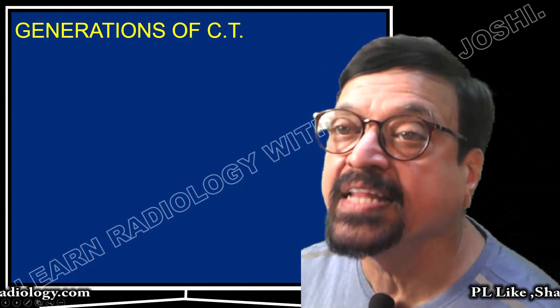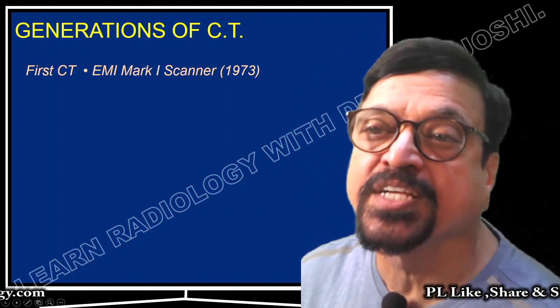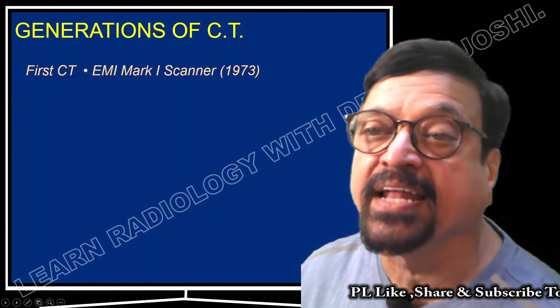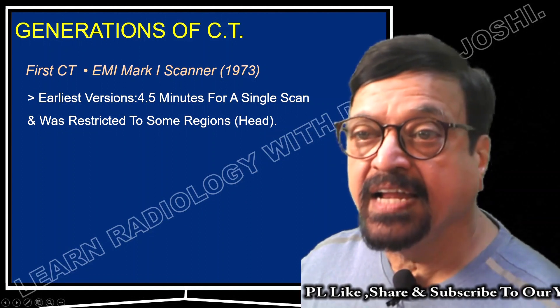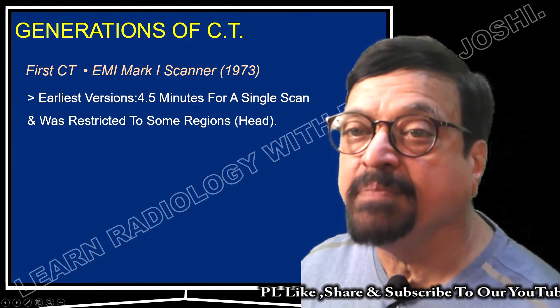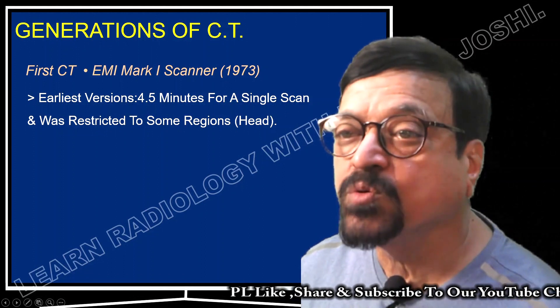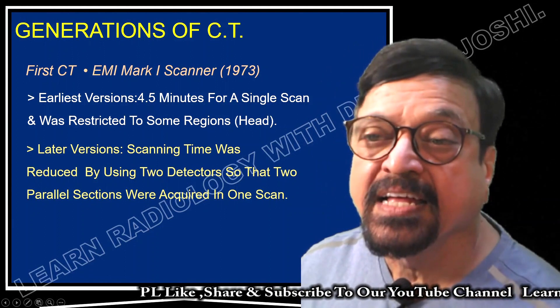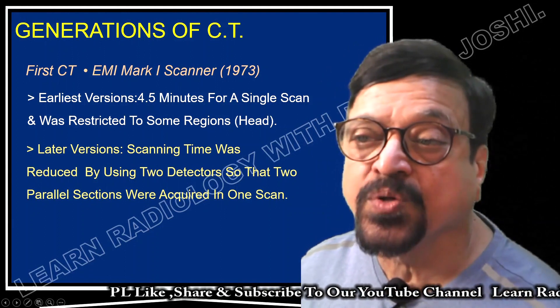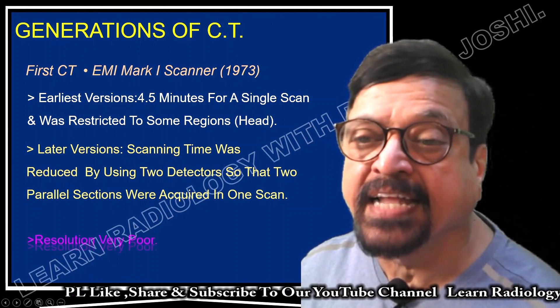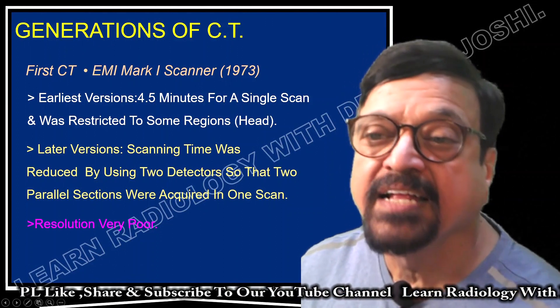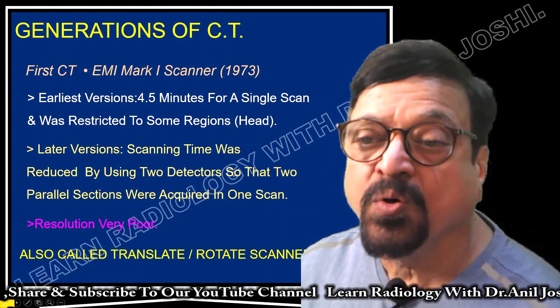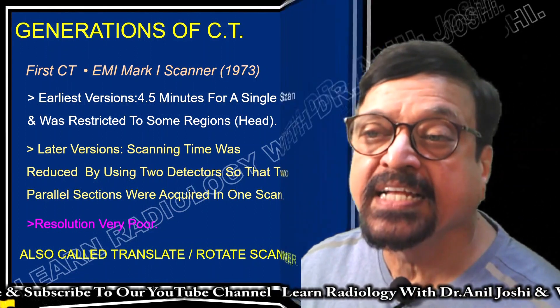What we are seeing today are third or fourth generation scans, which are really fast. The first CT was called the EMI Mark 1 scanner. The earliest version took 4.5 minutes for a single scan and was restricted to regions like head scanning only. Later, scanning time was reduced using two detectors so that two parallel sections are acquired, making it multi-slice, though resolution was not as good. These are called translate-rotate scanners.